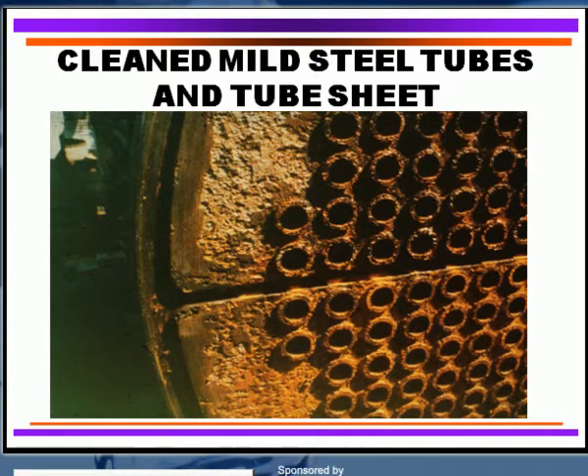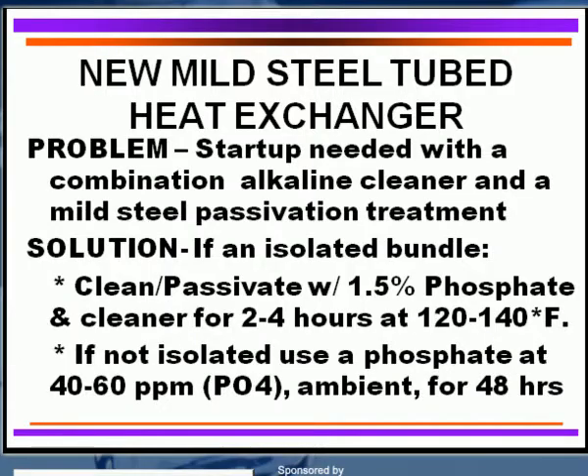So keep in mind you need to passivate this type of thing. For a brand new heat exchanger made of carbon steel tubing, remove the oils and greases with a cleaner, then use a mild steel passivation. If you have an isolated bundle, you can do this very rapidly — we have done that with a solution of 1.5% phosphate and cleaner for two to four hours at 120 to 140 degrees Fahrenheit, and it does an excellent job.